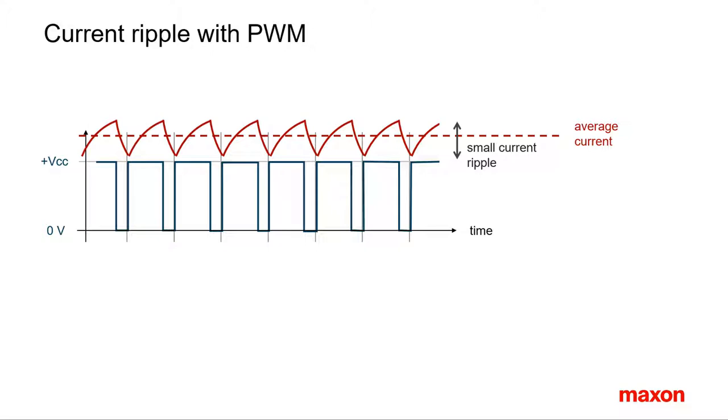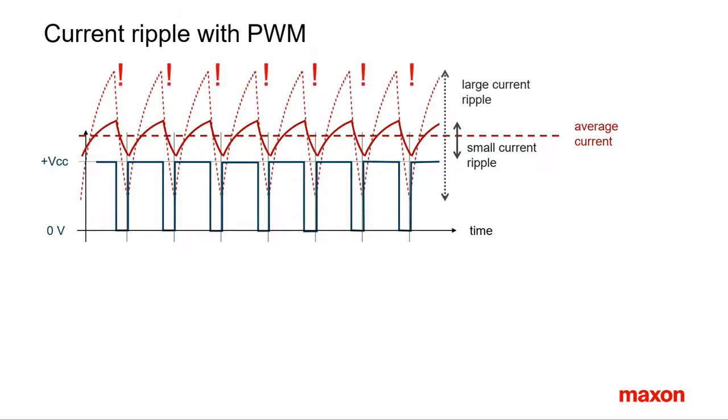Observe, however, it's still the average current that generates the motor torque. A large current ripple can lead to excessive motor heating, because the ripple peaks will heat up the motor more than proportionally. Hence, there is a strong interest in reducing the current ripple, and this is the main focus of this tutorial.